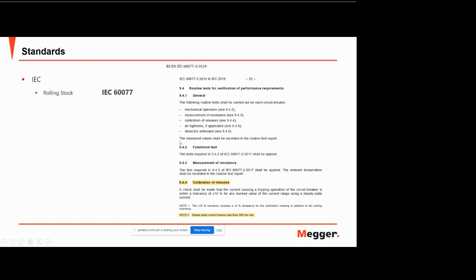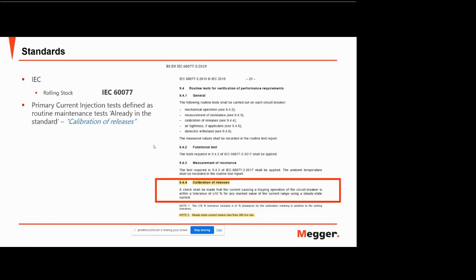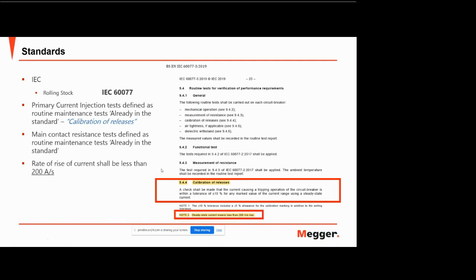The same also applies to the other IEC standard. This one is for rolling stock, IEC 60077. Again, 60077 states calibration of releases as a defined routine maintenance test. So this is your primary current injection test. A check shall be made that the current causing a trip operation of the circuit breaker is within tolerance. That is the check. Also, IEC 60077 stipulates testing the main contact resistance, again to make sure that there's no excessive resistance that may generate excessive heat. And 60077 also says the rate of rise shall be less than 200 amps per second.